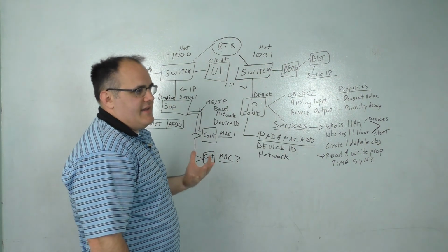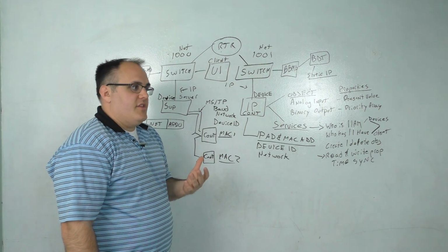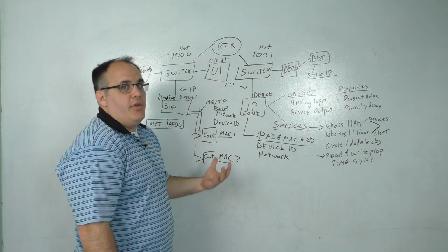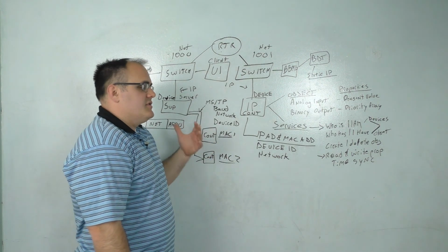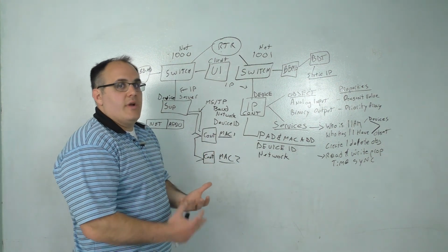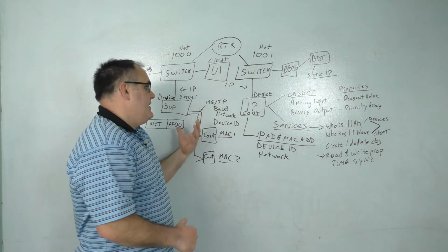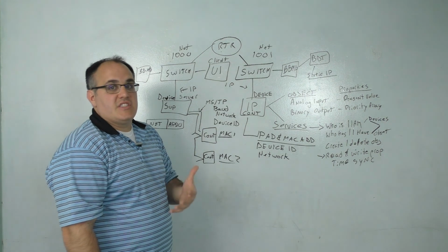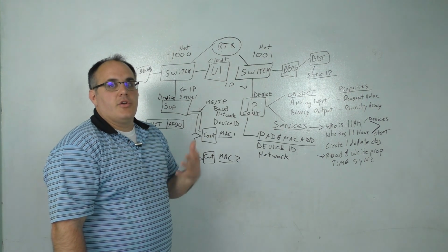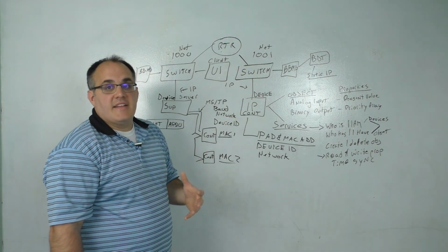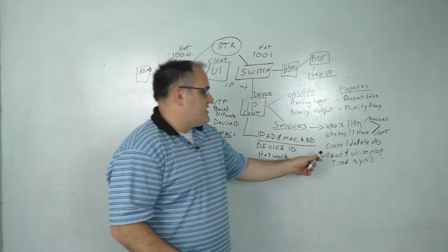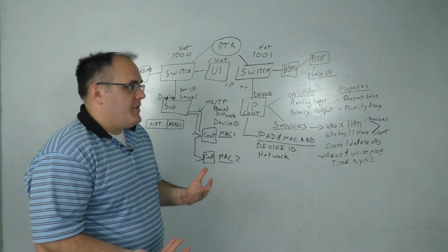There's kind of three kinds of services that happen. There's confirmed response complex, there's confirmed response simple, and then there's unconfirmed responses. So confirmed response complex is where you provide an actual value and you provide a status. It's complex. A simple confirmed request is where you just say the request ran. And then unconfirmed is where you don't even let the other requester, the client, know that the service request ran. Are you following me so far? Is this making sense? What's going on with services about how they're being used?